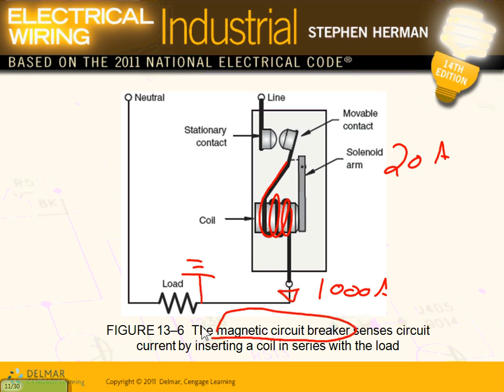A magnetic field, a very high magnetic field. There's a coil, and the magnetic field, like actuators, will create a force. Because you're momentarily putting a huge amount of current through a coil, and inside it there's a plunger that moves. So you create a force. That force will push these contacts right here. Can you see that? It pushes these contacts that are tied to it.